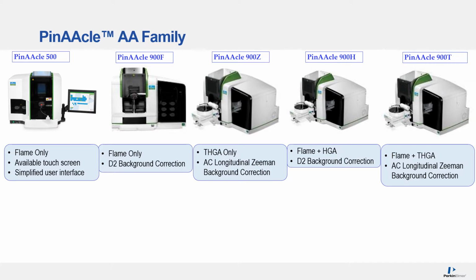It can contain up to 8 lamps at one time, whereas the PinAAcle 500 is limited to 4 lamps. The other benefit of the PinAAcle 900F is that it has full motorized adjustment of the burner height and depth to allow quick adjustment and optimization of the burner position.